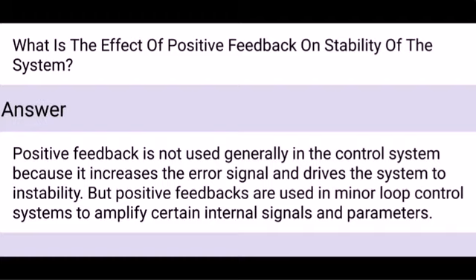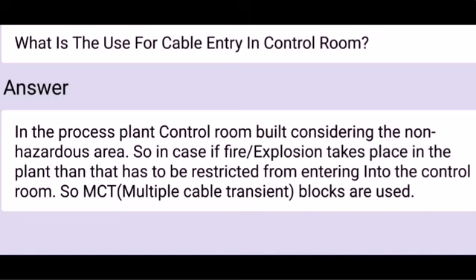What is the use of cable entry in control room? In the process plant, the control room is built considering the non-hazardous area. So, in case a fire or explosion takes place in the plant, then that has to be restricted from entering into the control room. So MCT, multiple cable transit blocks, are used.